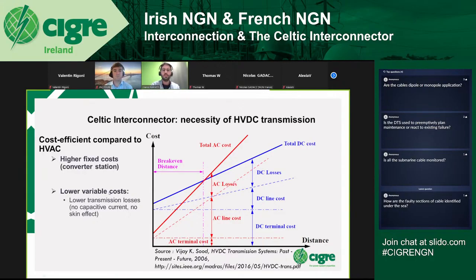However, we have lower variable costs in DC transmission, due to lower transmission losses. We have no capacitive current and no skin effect in HVDC transmission. All this creates a break-even distance, shown here in purple or pink color. This break-even distance is created once the total AC cost surpasses the total DC cost.